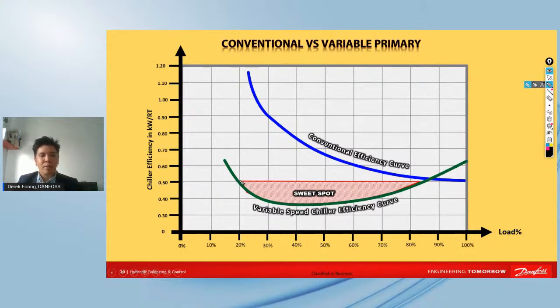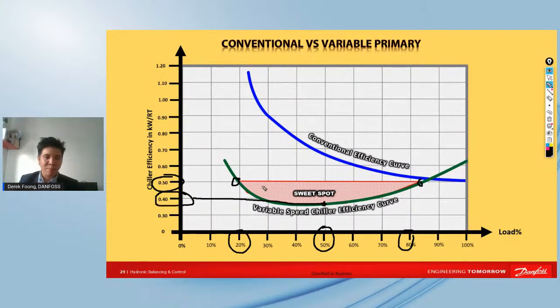So of course, if you want to fully occupy most of the capacity, let's say between 20% load and 80% load, it will be most of the time below 0.5 kilowatt per ton. But of course, it depends on the temperature set point and how the condenser is sized. Now, we always remember that the lower the load, the more efficient it is. For example, at 50% load, this can be around 0.4 kilowatt per ton, compared to around 0.65. So the differences are huge. It's almost between 60 and 70% difference in energy consumption during part load.